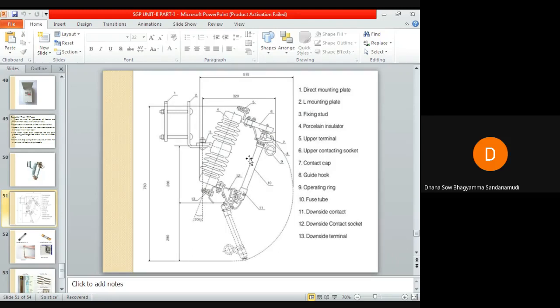So whenever a fault occurs, of course, an arc is struck between the terminals of this fusing element. The fusing element will immediately reach its melting point and blow out, and the arc is struck. Under fault conditions, the arc heat will decompose the boric acid into water vapors. These water vapors blast and deionize the arc path and prevent arc reignition after a natural current zero. What is natural current zero and what is reignition, I will discuss later in this unit.